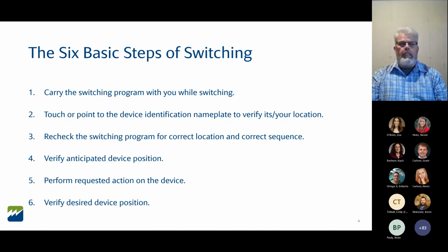First, you carry the switching program while you're switching. Then you touch or point to the device identification nameplate to make sure you're in the right location. You recheck the switching program for the correct location and correct sequence, then verify the anticipated device position. Number 5 is performing the requested action on the device in a safe manner, and number 6 is verifying the desired device position. So if I was opening a disconnect switch in a substation, I want to make sure I have all 3 phases open as directed.